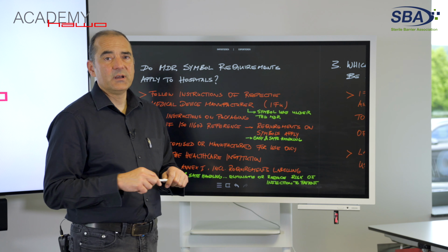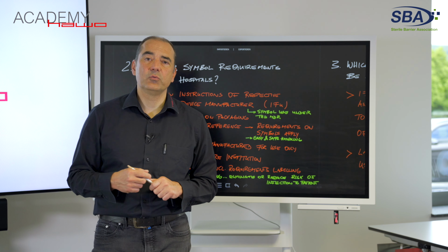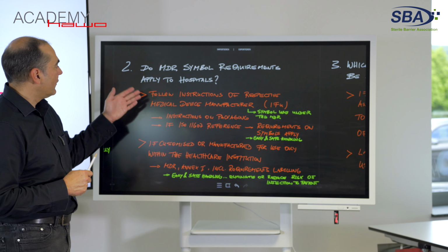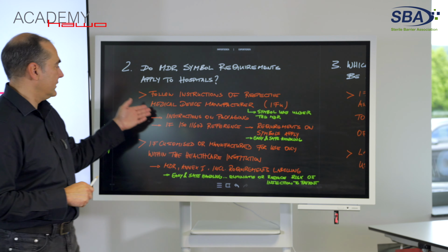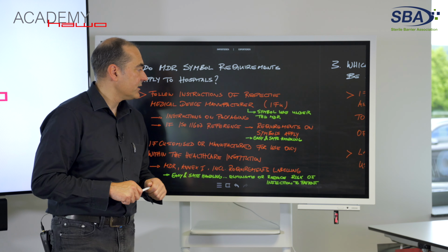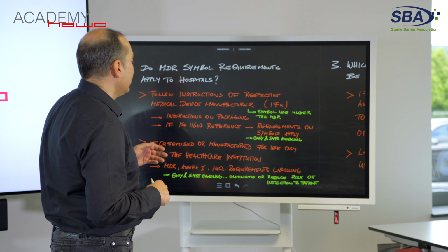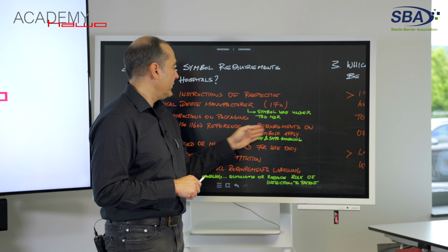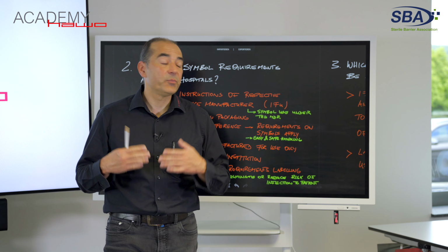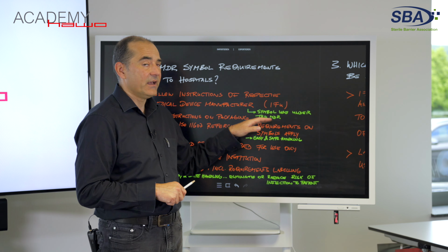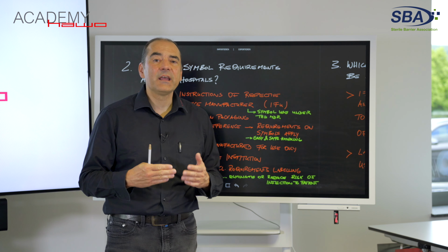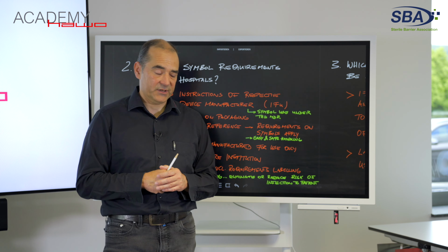It can be presumed that medical device manufacturers will stick to symbol printing anyway. So following the instructions, we have instructions on packaging, and if there's an ISO 11607 reference given, then we have a requirement on the symbol that applies as well, from the perspective of easy and safe handling. Easy and safe handling, again a means of risk minimization.